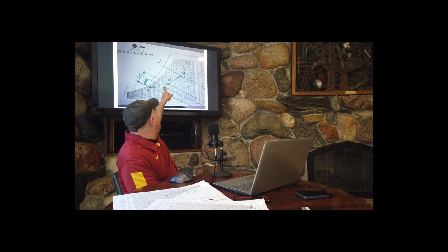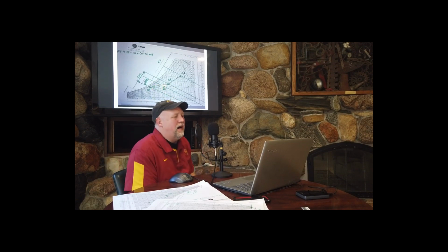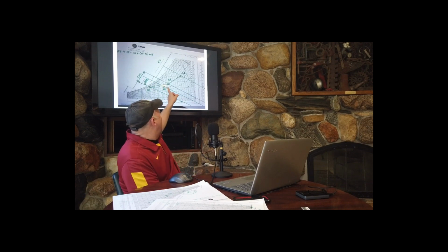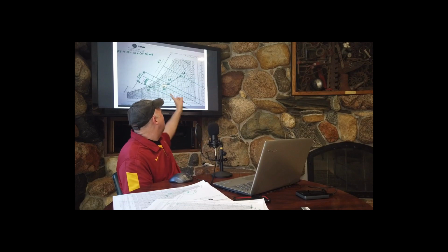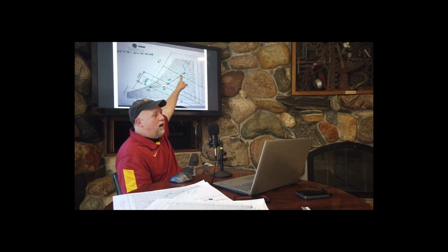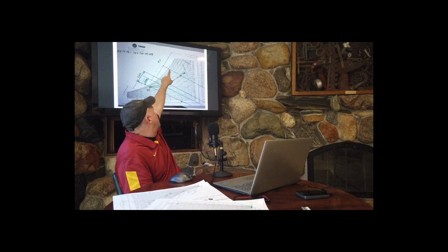The reason we call this a loop is that this air gets returned to the air handler. Once it's at the air handler, we're going to exhaust some of it and make it up with outside air. Here's our next point. Our outside air point, which is at 95 degrees Fahrenheit dry bulb, 78 degrees Fahrenheit wet bulb, right here.